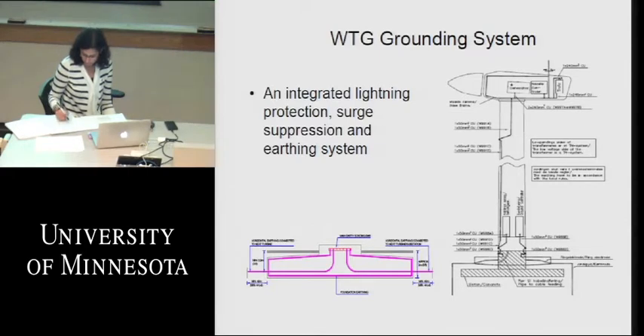Now, this is good for grounding faults, for 60-cycle faults, but high-energy faults and high-frequency faults from lightning tend to want a lower impedance path for its surge impedance. So the high-frequency component of the lightning strike. And so what you'll see is there's two conductors that come out of the foundation or out of the wind turbine and go horizontally in the soil about 3 feet deep for about 40 meters on either side of the wind turbine. And that is more of the lightning protection side of this integrated lightning and earthing system, where the foundation is more of the grounding or the 60-cycle fault protection for the grounding system.